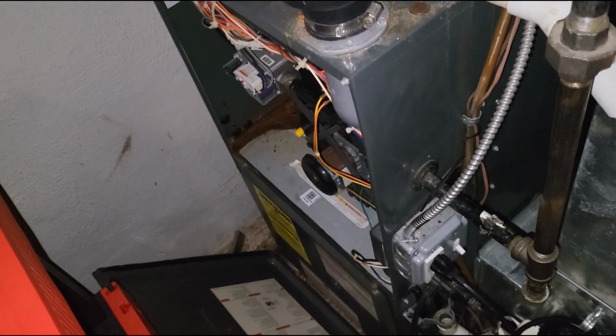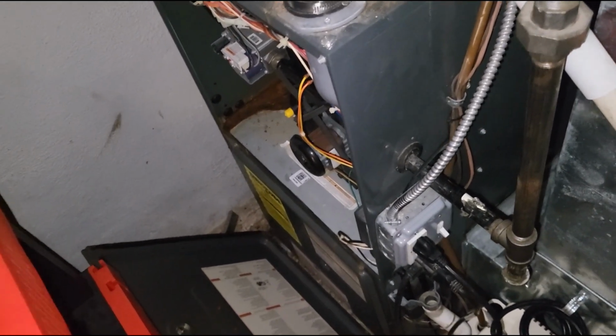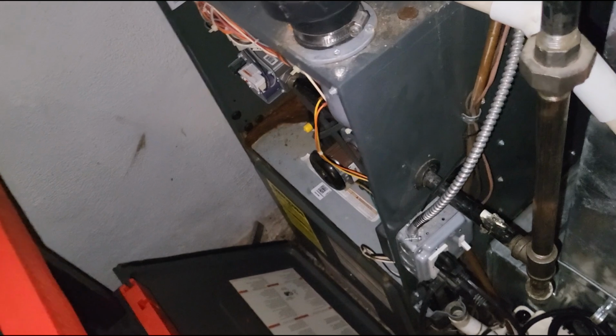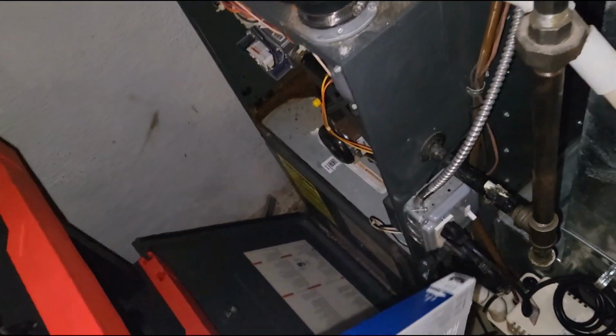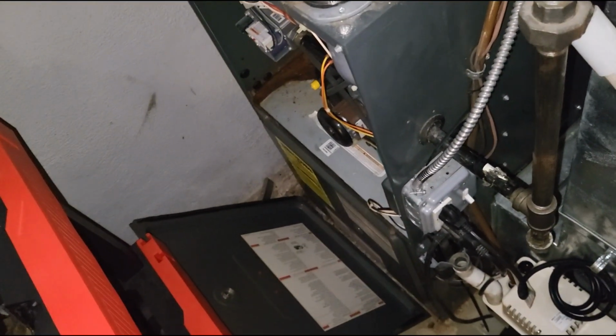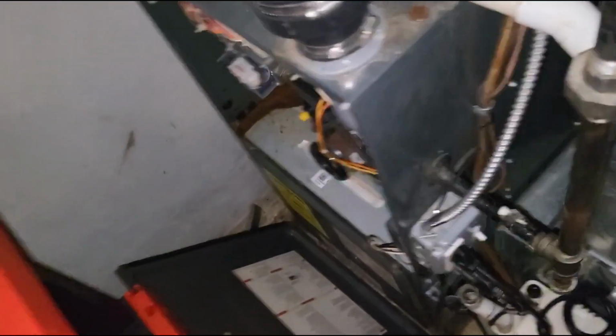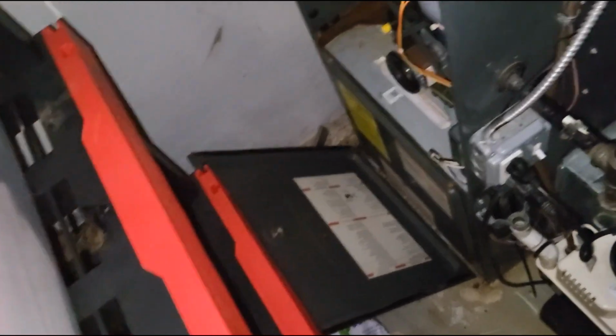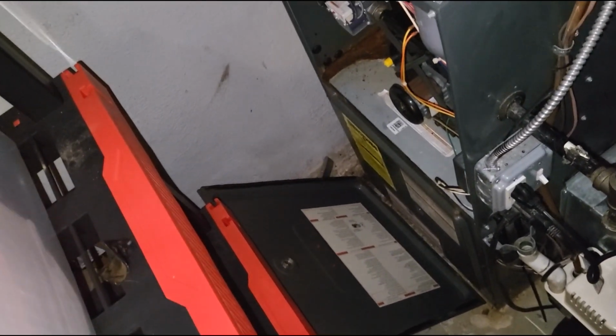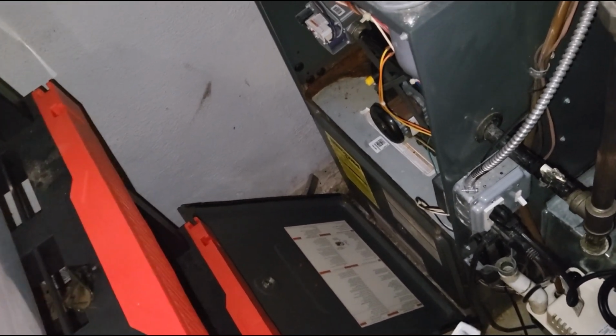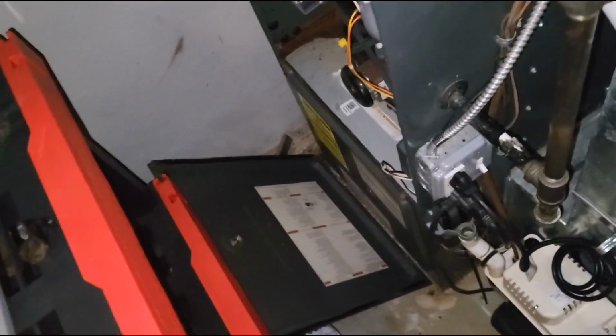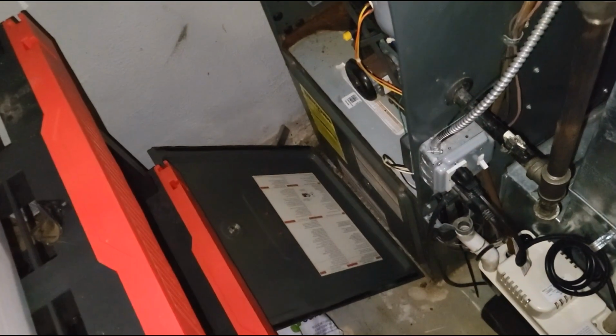If that heat exchanger is leaking, that means the heat exchanger is not going to be in the negative pressure. So guys, putting 2 and 2 together, I'm all for letting things run out until it dies. But guys, the point of the maintenance is to make sure the customer is aware of potential problems, so now they're not scrambling, calling you 3 o'clock in the morning on a 20-degree night saying your heat isn't working, and now they're forced to replace a furnace before they really wanted to.